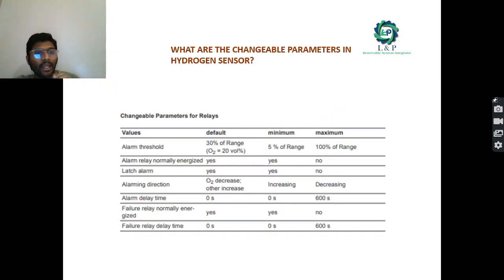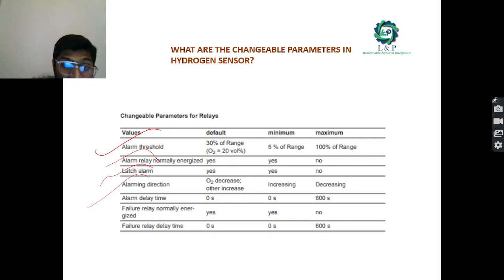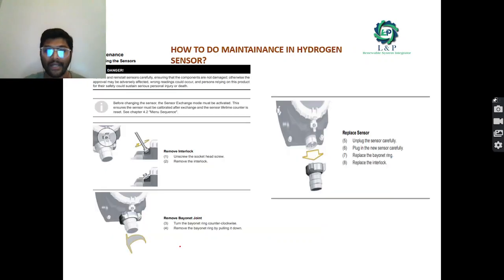So what are the changeable parameters inside this hydrogen sensor? You can change the alarm threshold value. You can change the alarm relay, whether it needs to be energized or not energized. You can change the latch alarms, you can change the alarm directions, and you can set the alarm delay timings. And you can make the failure relay normally energized, and set the delay timing for the failure relay.